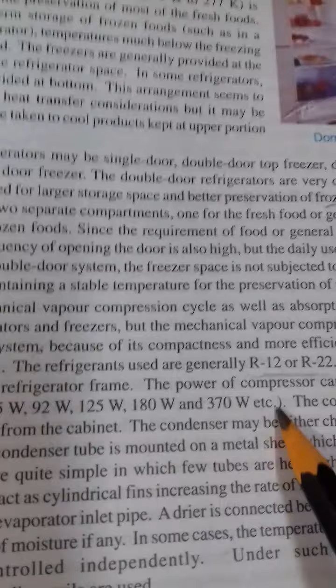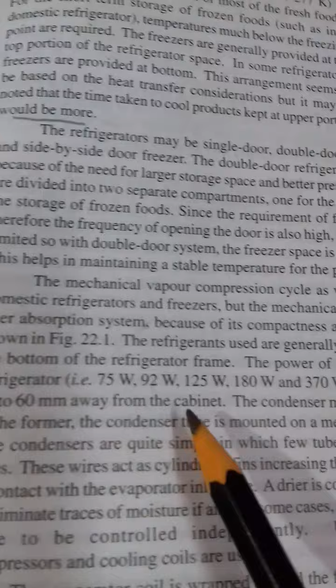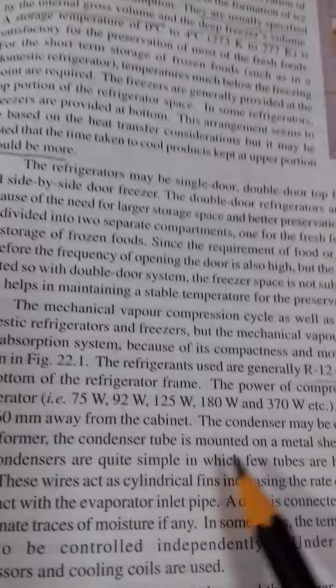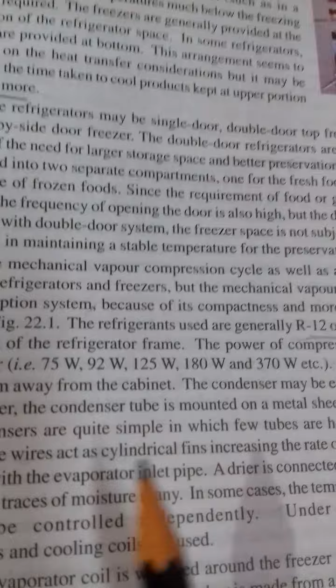The condenser is put at the back about 40 to 60 mm away from the cabinet. The condenser may be either chassis type or tube type and wire type. In the former, the condenser tube is mounted on a metal sheet which acts as a fin. The tube and wire type condensers are quite simple, in which a few tubes are held tightly under a frame from both sides.